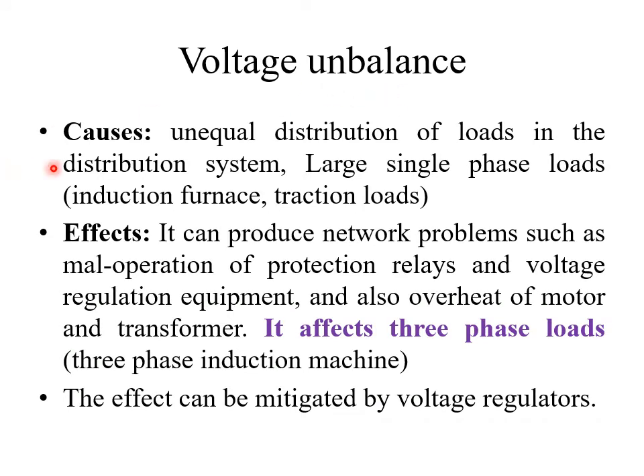The causes of voltage unbalance: we know there are three phases, and if one phase is heavily loaded — meaning the distribution of loads is not equal — it leads to voltage unbalance. Practically, it is very difficult to balance the three-phase system, especially when single-phase loads are used, making one phase more loaded than others. This is the basic cause of voltage unbalance.